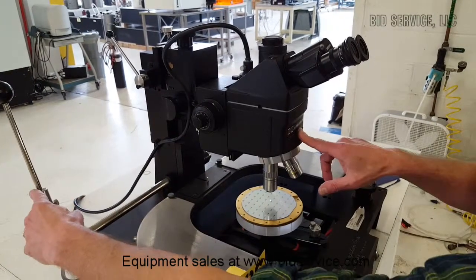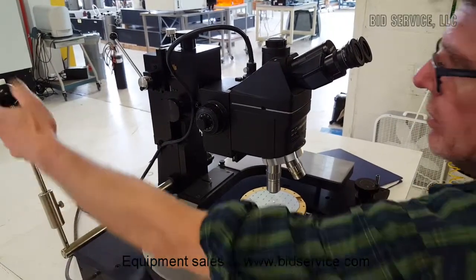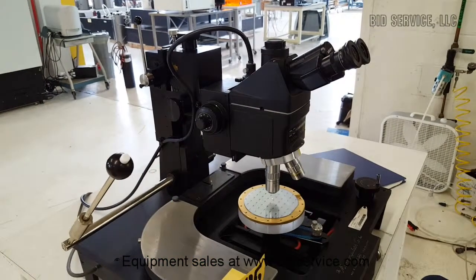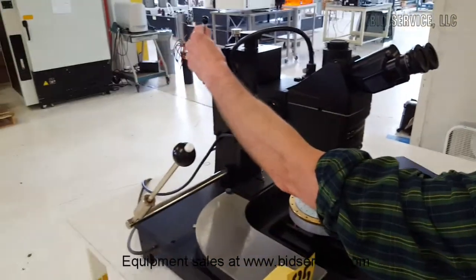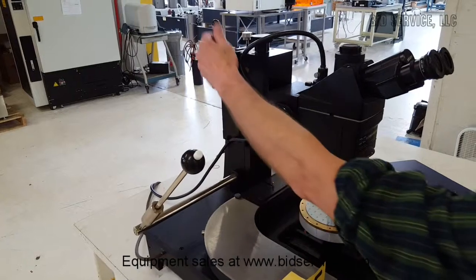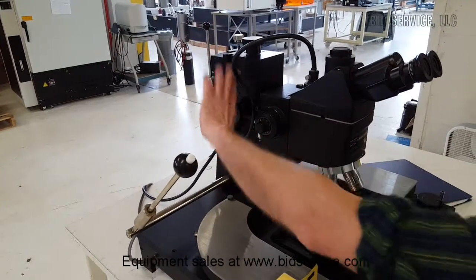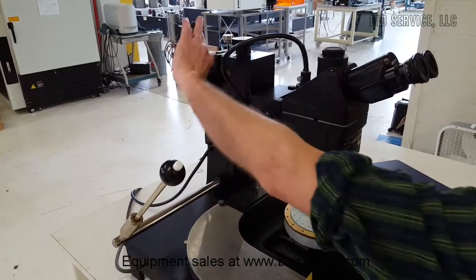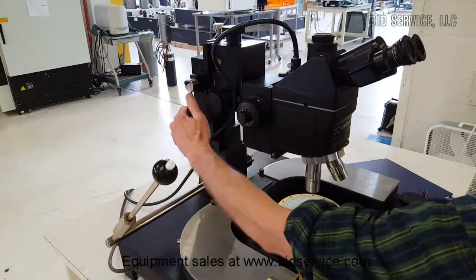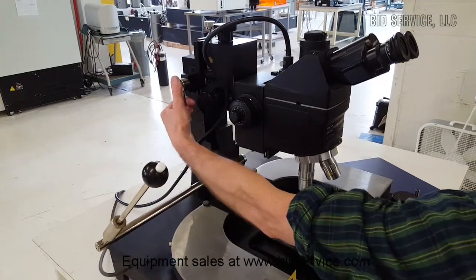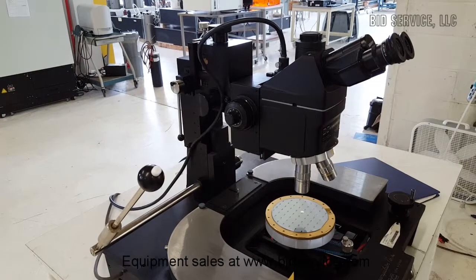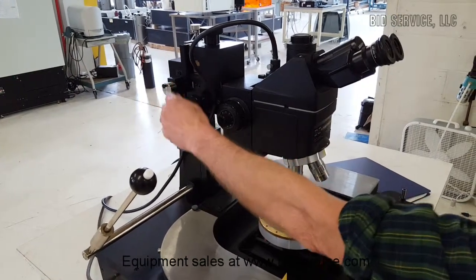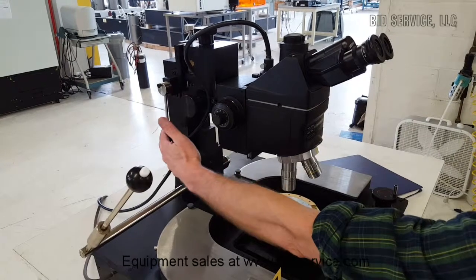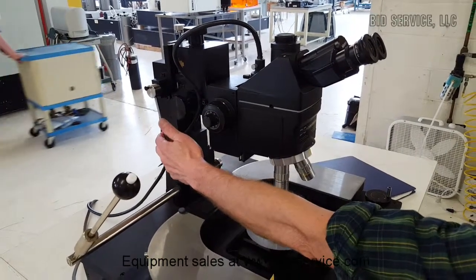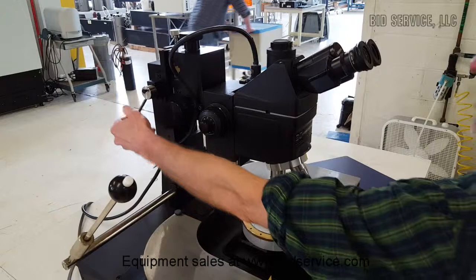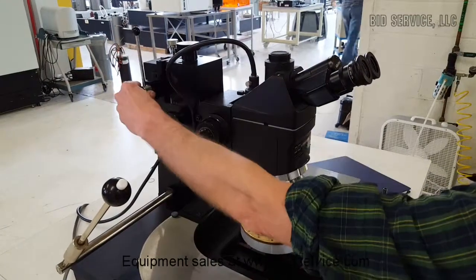Again, this microscope's moving up. And to release it, we'll bring this down. This also has the option that you can lift the microscope independent of the platen. And this is the down position here with the knob facing up, and to lift the microscope, bring this over to this position and lock it in place by using this screw on this push pin. To release it, I just took a little weight off the microscope, and you see the pin popped out, and it'll allow you to bring it back down.